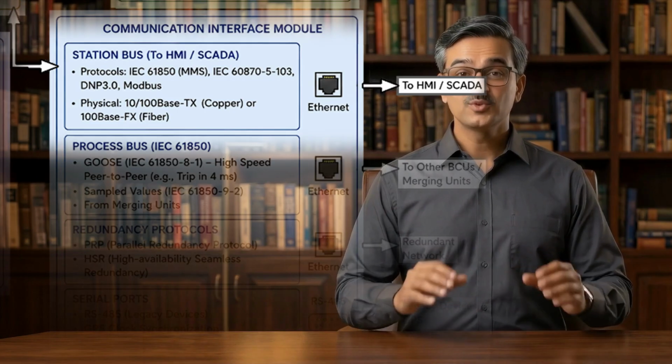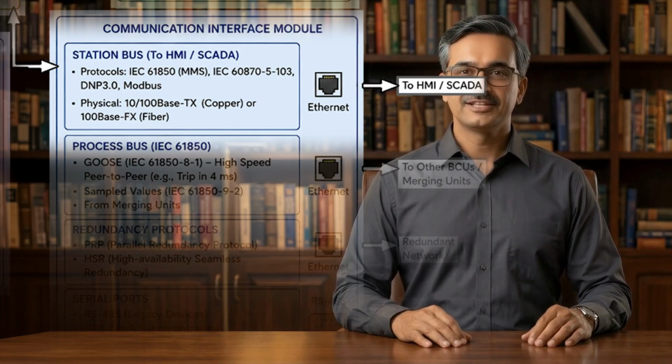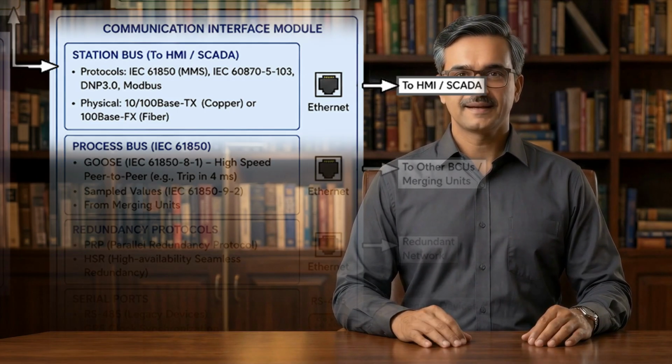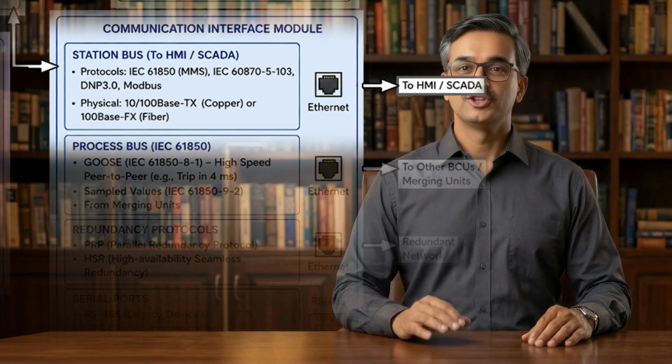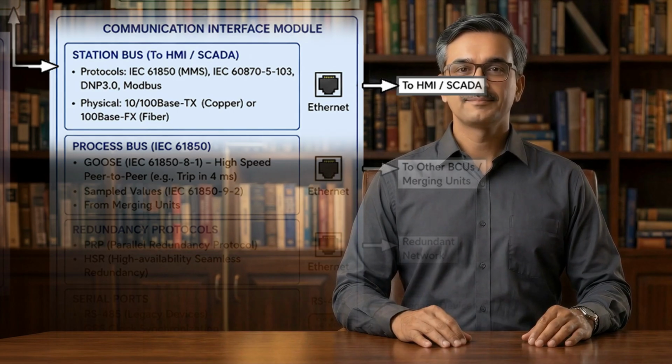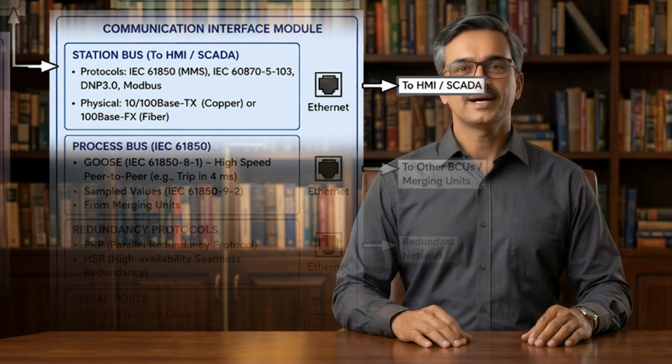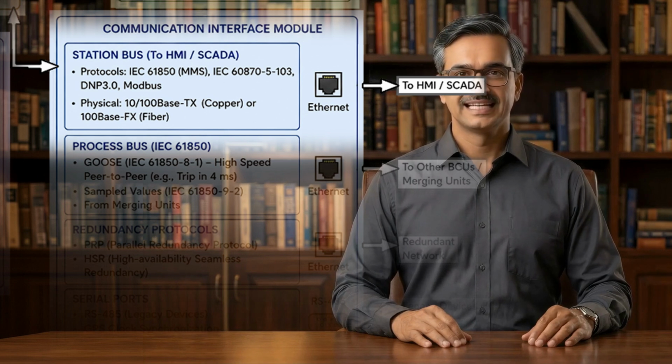Protocols supported include IEC 61850, MMS, IEC 60870-5-103, DNP 3.0, and Modbus. Physically, it uses 10/100 base TX copper Ethernet or 100 base FX optical fiber ports.